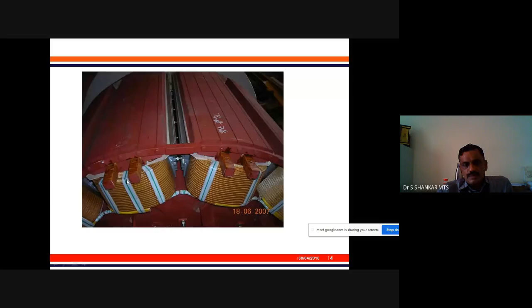they will have some layers, some insulation over this, but because of this extension to and fro, the insulation gets worn off. Automatically, there is a short circuit, which leads to catastrophic failure. This is the problem given to the industry. So we need to find out what happens during rotation and what is the maximum amount of expansion possible, whether it will go beyond the air gap or not. The air gap may be approximately 1 mm or 2 mm. If it expands more than 2 mm, what can we do?